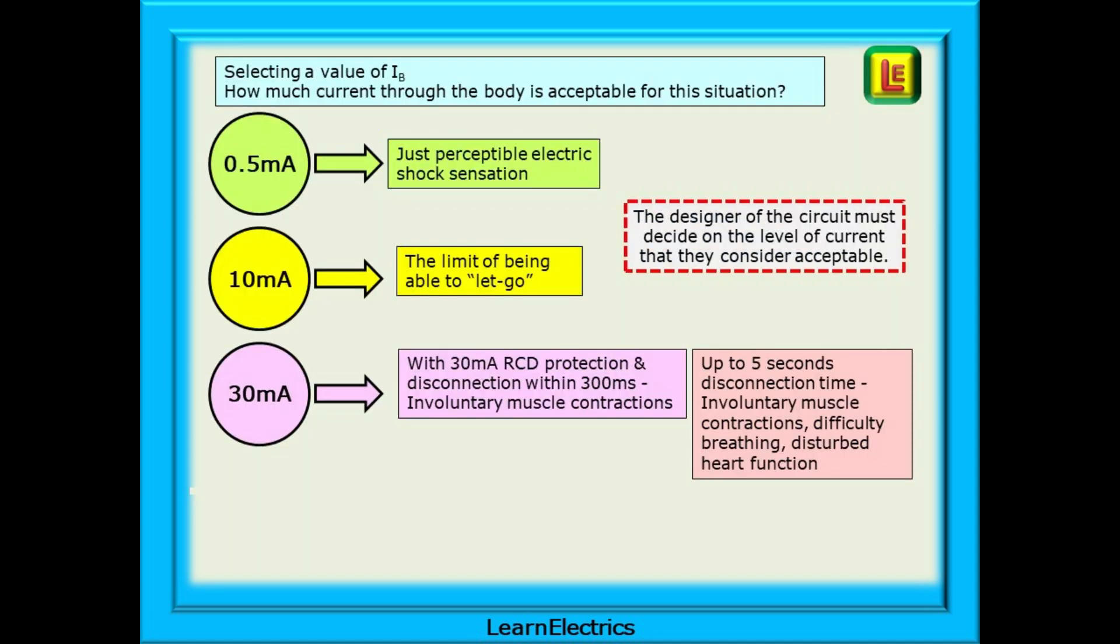This slide shows the effects of electric current on the human body when the line voltage is 230 volts AC. At less than 0.5 milliamps, the user will barely feel an electric shock. As the current increases, there comes a point where it is difficult to let go of a conductive part or cable. At 30 milliamps, we are approaching the limit of what is a recoverable electric shock. Involuntary muscle contractions will be noticed and an inability to let go. It is recommended that an RCD is installed to disconnect the supply in 300 milliseconds or less, and this will help to make the shock recoverable. A longer exposure to shock will make breathing difficult and may cause a disturbed heart function and more serious problems.